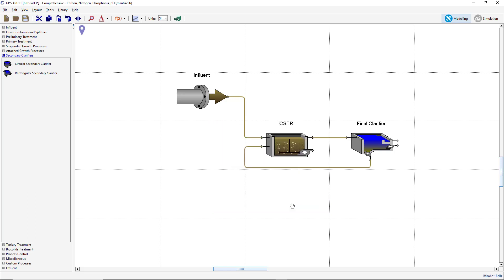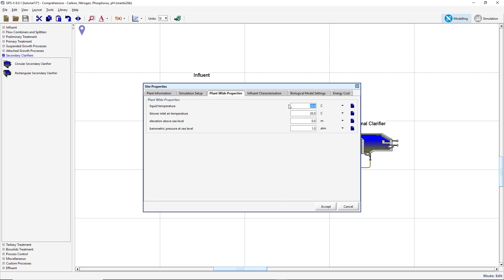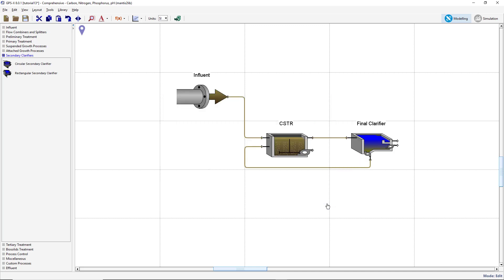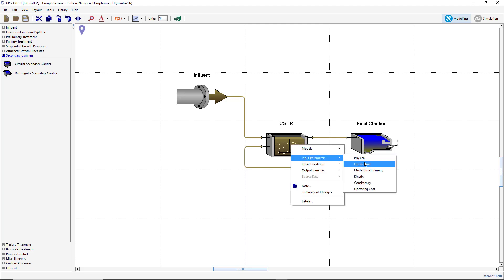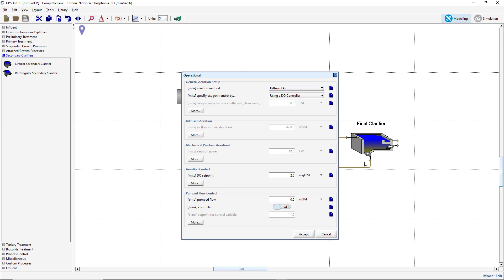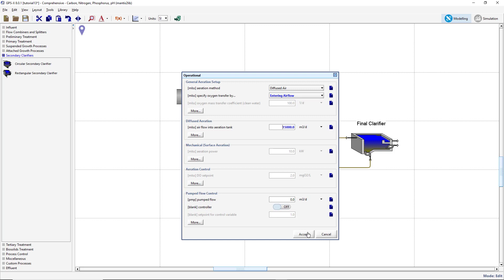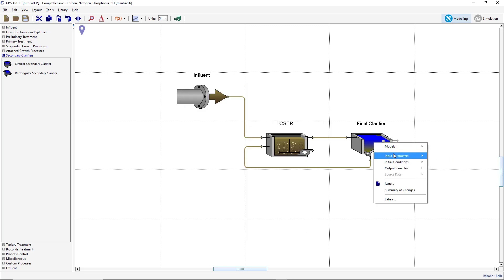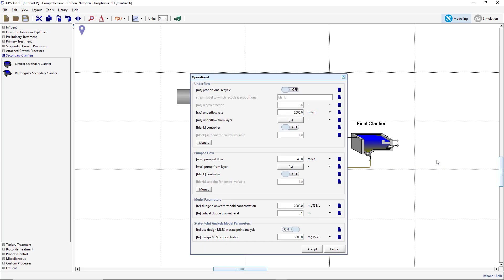We will be simulating this model under cold winter conditions. Open the Site Properties menu and navigate to the Plant Wide Properties tab. Change the liquid temperature to 10 degrees Celsius. Next, we'll change some of the object parameters in the model. Right-click on the CSTR and select Input Parameters, Operational. Set the Specify Oxygen Transfer By variable to Entering Airflow. Set the air flow into the aeration tank to 15,000 meters cubed per day, then accept the form. Right-click on the clarifier and select Input Parameters, Operational. Set the pump flow to 70 meters cubed per day and accept the form. Save the layout.